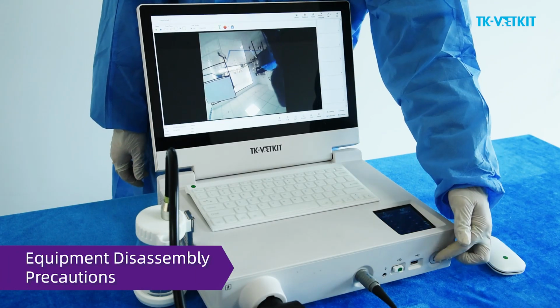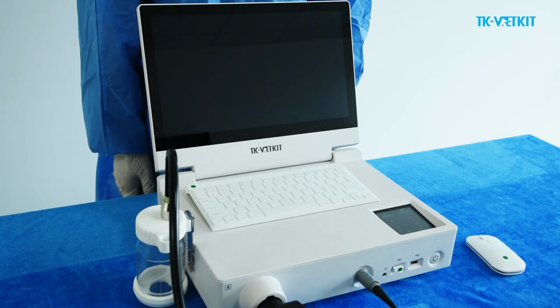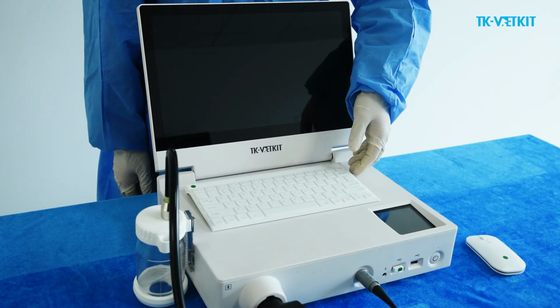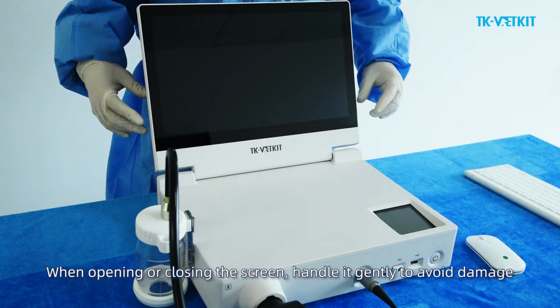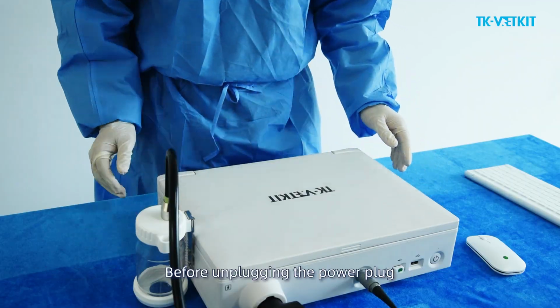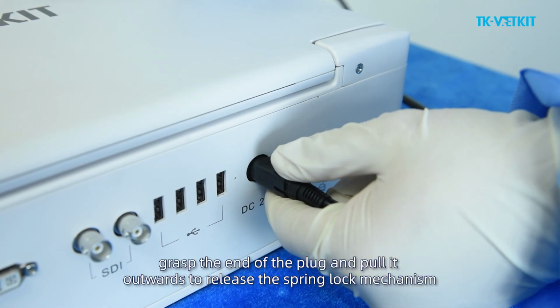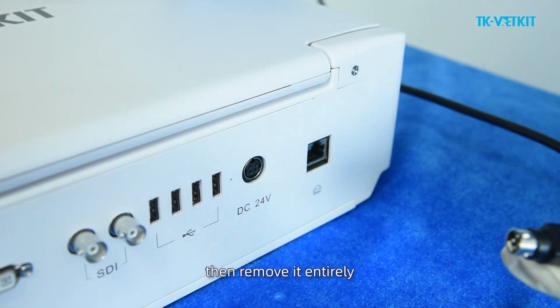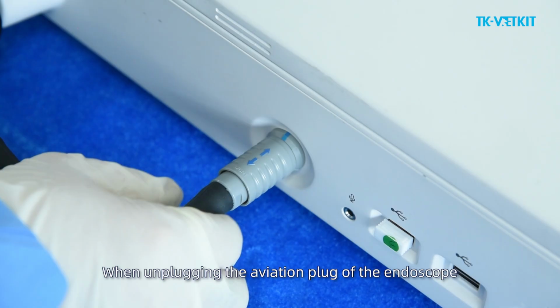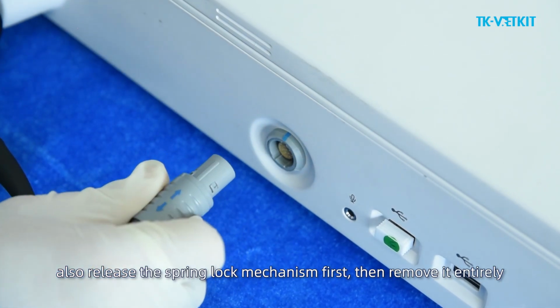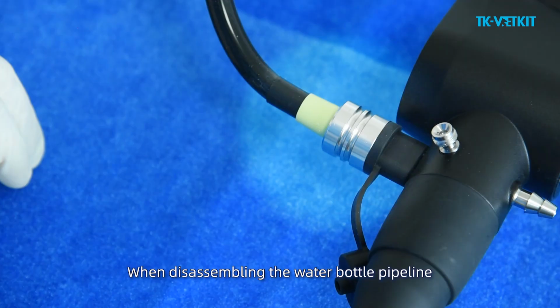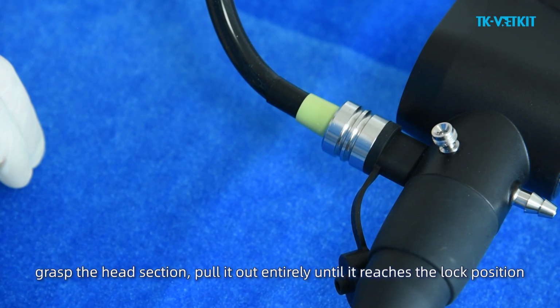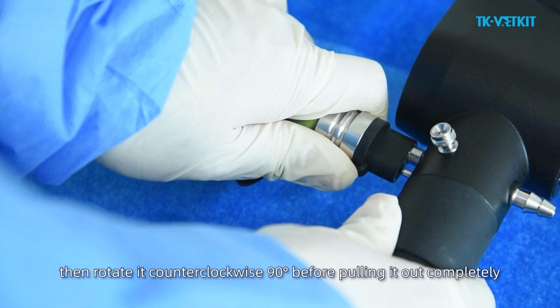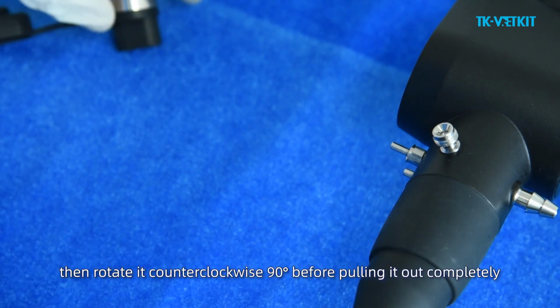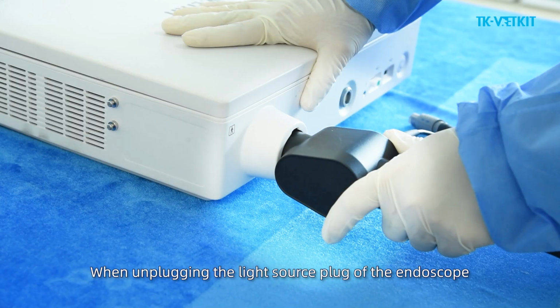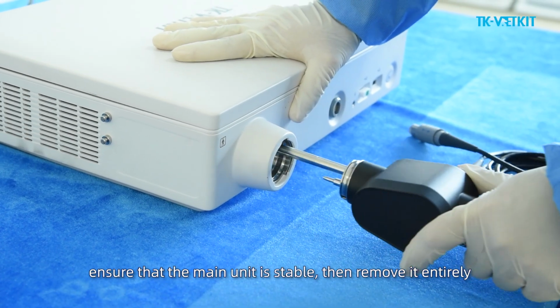Equipment disassembly precautions. When opening or closing the screen, handle it gently to avoid damage. Before unplugging the power plug, grasp the end of the plug and pull it outwards to release the spring lock mechanism, then remove it entirely. When unplugging the aviation plug of the endoscope, also release the spring lock mechanism first, then remove it entirely. When disassembling the water bottle pipeline, grasp the head section, pull it out entirely until it reaches the lock position, then rotate it counterclockwise 90 degrees before pulling it out completely. When unplugging the light source plug of the endoscope, ensure that the main unit is stable, then remove it entirely.